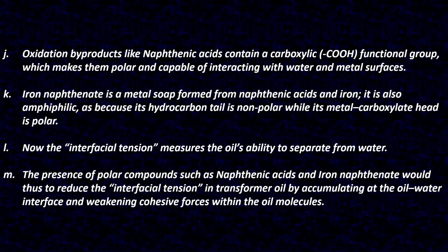Now, the interfacial tension measures the oil's ability to separate from water. The presence of polar compounds such as naphthenic acids and iron naphthenate would thus tend to reduce the interfacial tension in transformer oil by accumulating at the oil-water interface and weakening cohesive forces within the oil molecules.